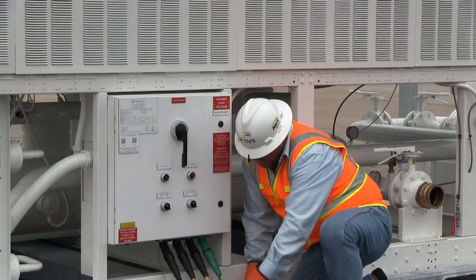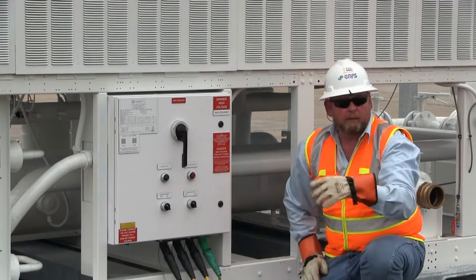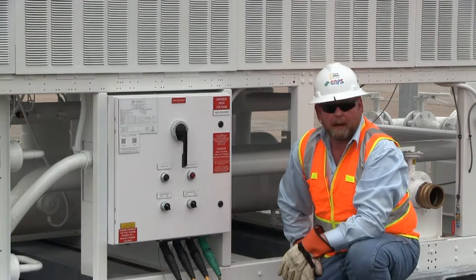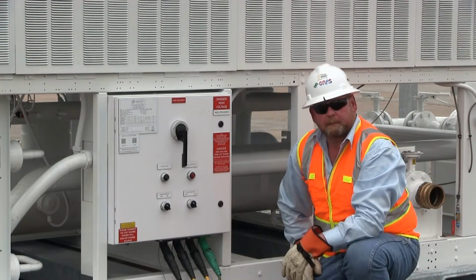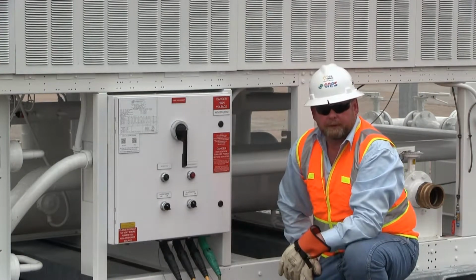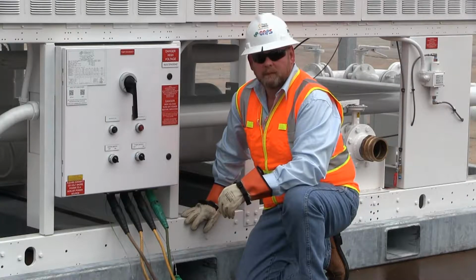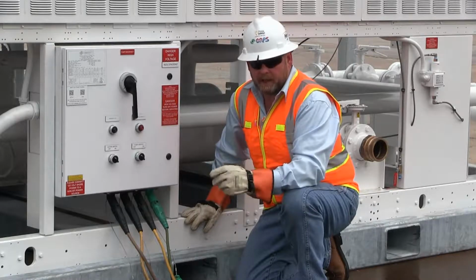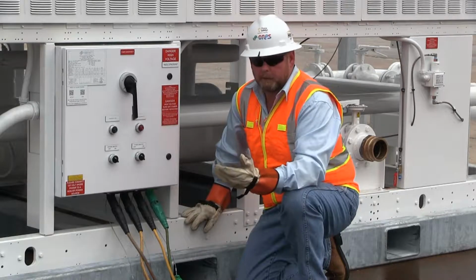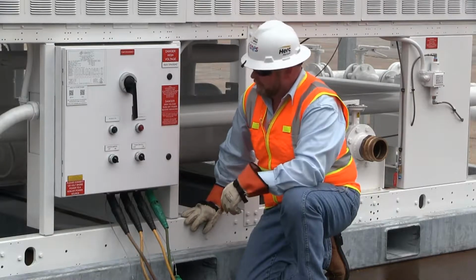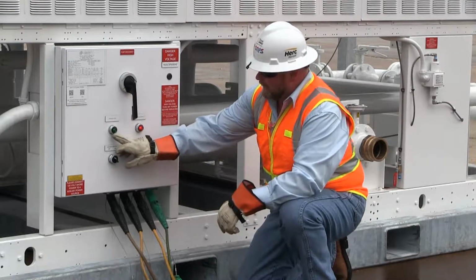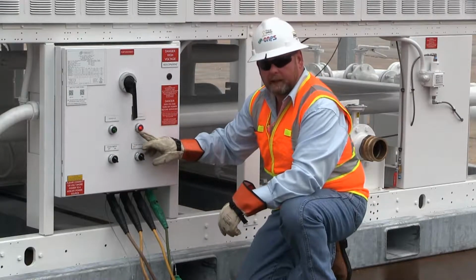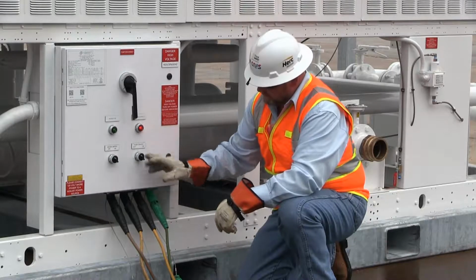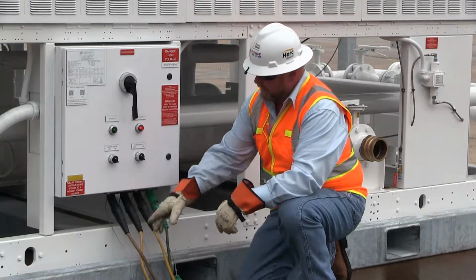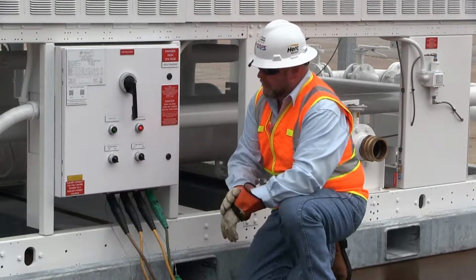Now that we have the power hooked up, we're going to remove our lockout tagout from our primary power supply. We're going to energize the machine and check our rotation. Okay, now we've energized our main power feed, so we're going to turn the breaker on and check rotation. Okay, our power lights come on, but we have our phase incorrect light on as well. That indicates that two of our phases are backwards. That has the machine completely locked out.